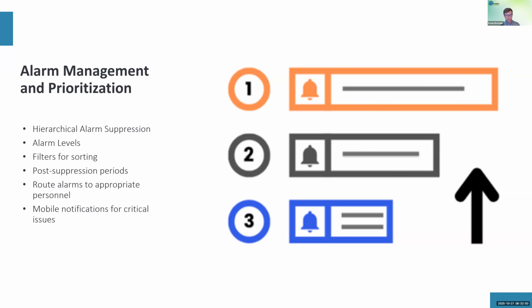And an example of that is creating, let's say, an AHU system. You have an air handler that serves a bunch of terminal units. If that air handler fails, we're also going to see a bunch of alarms at all the terminal units. But those alarms at the terminal units are not where facilities' attention needs to be. It needs to be at the upstream equipment. So by creating a system where those downstream alarms are suppressed, like all the alarms at the terminal units, we block out that noise and instead highlight that it's the air handler that is the critical issue for facilities.